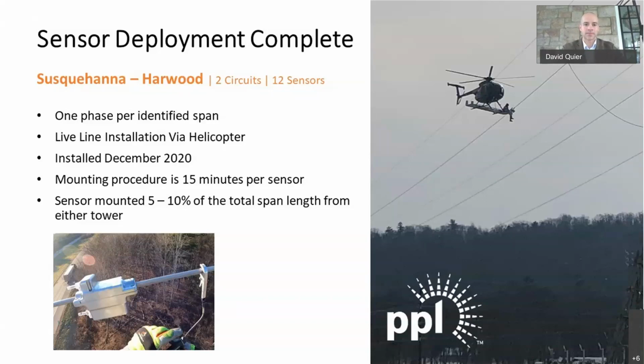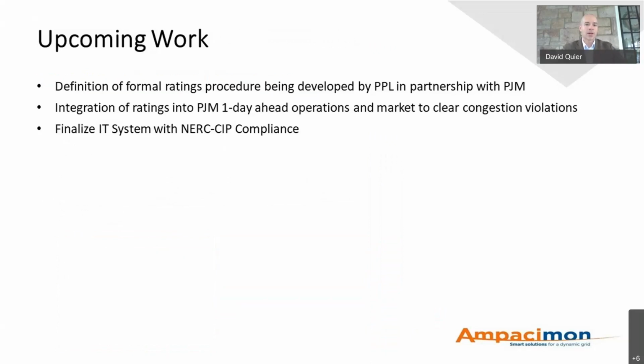And then our last slide, please, Joey. So upcoming work in getting into real-time ratings does introduce certain aspects we really never thought of before. For instance, if the ratings change based on how fast or slow the wind is blowing, temperature, and time of day, you get into questions like how often will we allow the rating to change, and how drastically will we allow that rating to jump around. As well as, if we would lose communication to the sensor, what's our fallback rating, which is pretty clear cut. We just fall back to our original static rating, but we had to think through things we hadn't had to think through before.